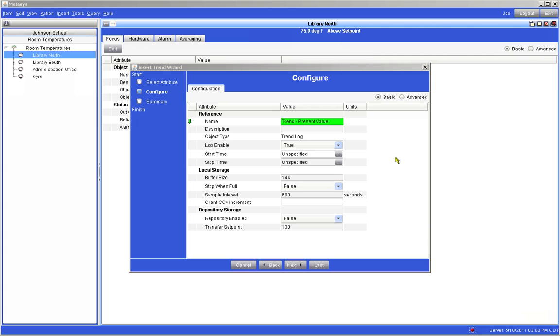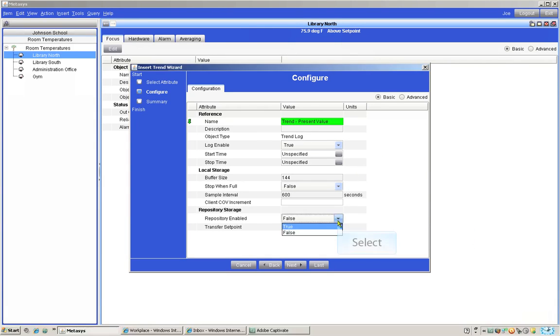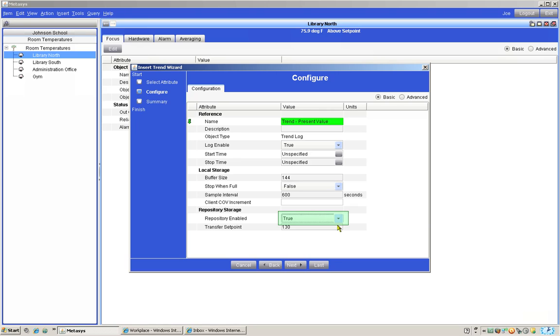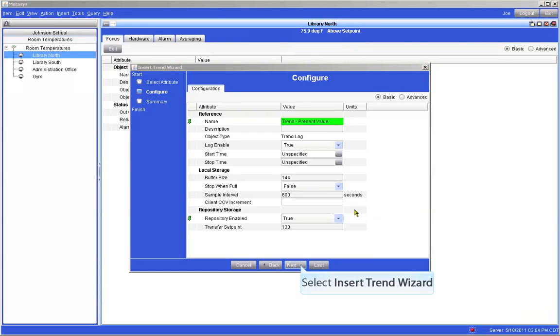Also in this area is a section called repository enabled. We will change that from false to true. This will enable the trend to store all of our temperature readings for future recall. That will allow us to recall temperatures from the first day the trend was created. We may want to recall trended temperatures years from now.